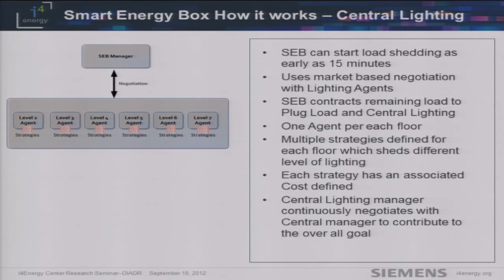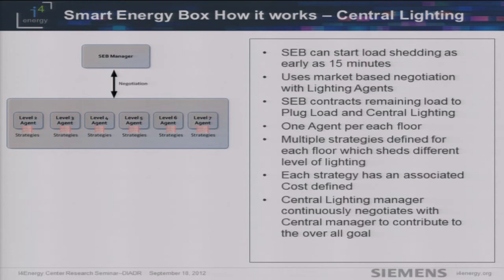For central lighting, the manager inside the Smart Energy Box uses an agent-based negotiation adaptive approach. There are agents defined for each level of lighting in this building — six agents in total. Each level has multiple strategies defined; for example, if the total power is 50 kilowatts, strategies might offer shedding of 20, 30, or 35 kilowatts — the maximum that can be shed without turning off all lights. During demand response, agents communicate with each other and promise how much they can shed, trying to collectively achieve the goal.